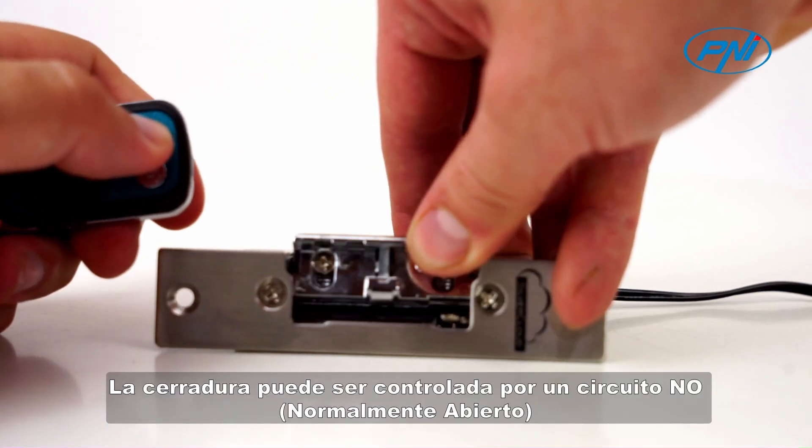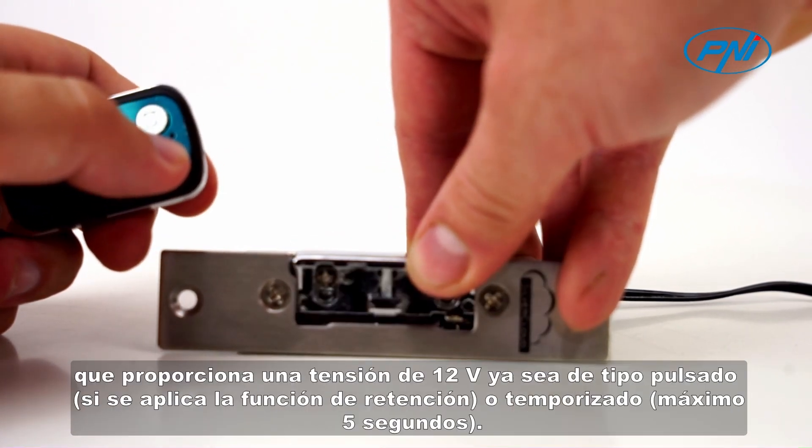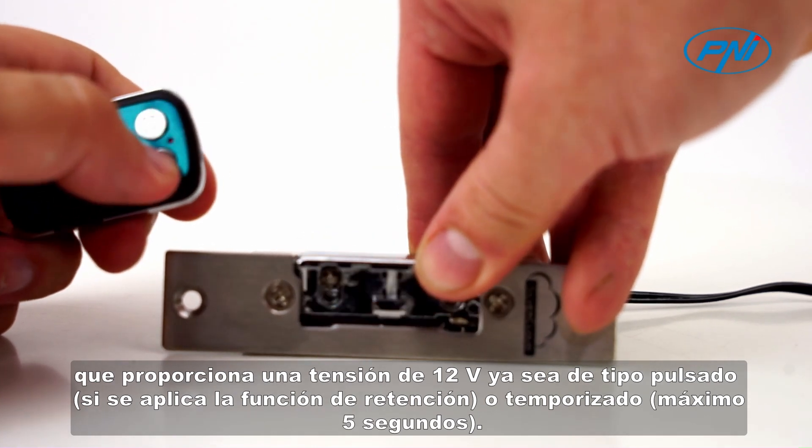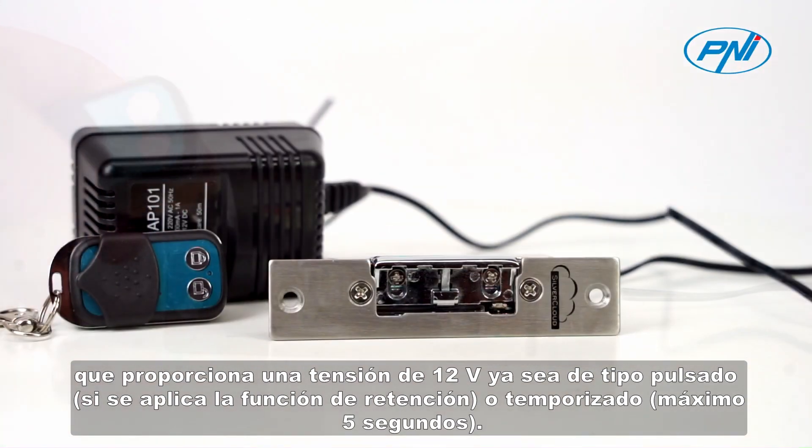The lock can be controlled by an NO normally open circuit that provides a voltage of 12V, either pulse type if the retention function is applied, or timed — maximum 5 seconds.